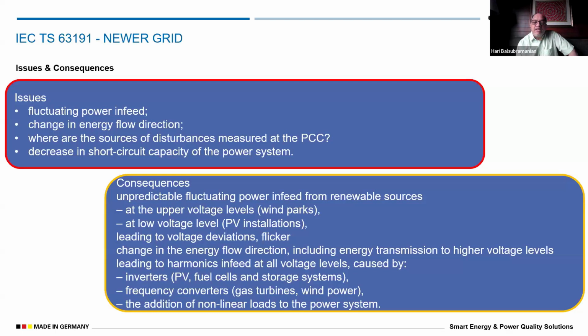At PV installations, it becomes very important where the PV gets connected to the system. Connect it at the wrong end and you face more complications handling power factor or other aspects of the system. Voltage deviations occur frequently because not all sources are active always—they switch on and off, and the flow direction also changes. These are common consequences of the newer grid.